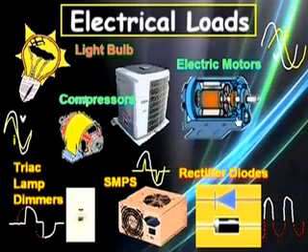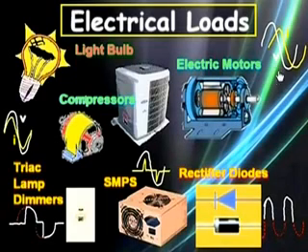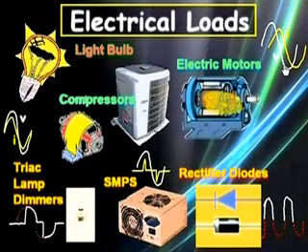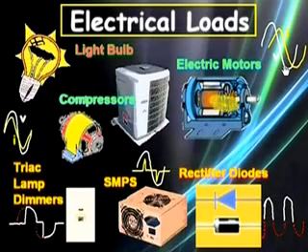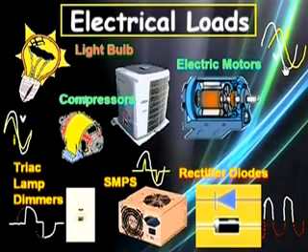A big industrial motor like this one, with its many inductive windings, causes a phase displacement between the AC current and voltage, and creates additional reactive amps needed to expand and collapse its magnetic fields. These reactive amps do not produce useful watts.